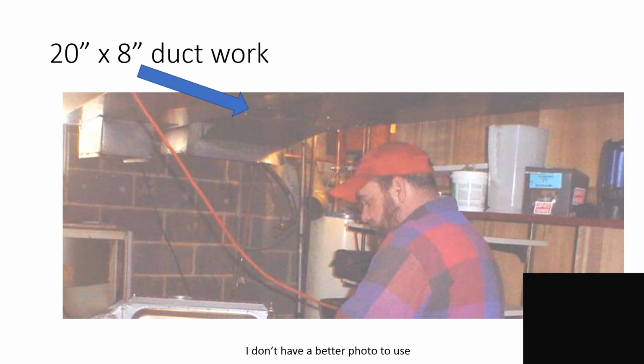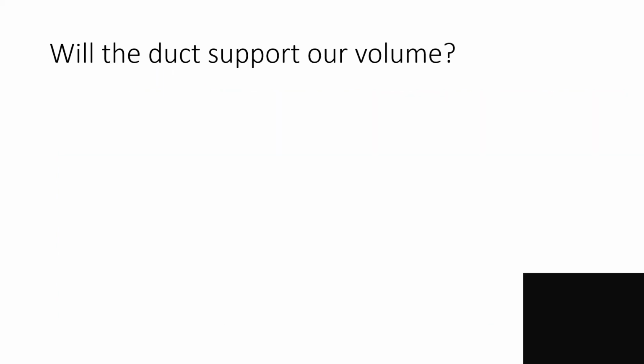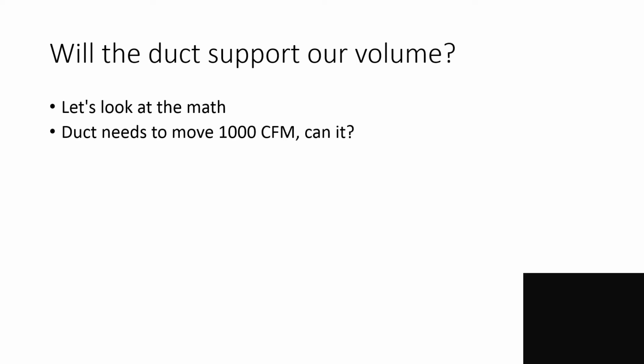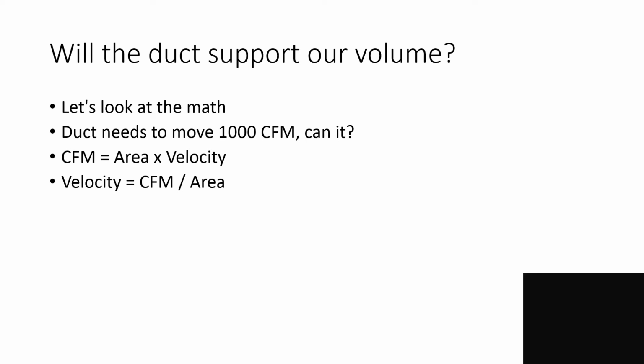We got 20x8 ductwork on an existing system and we're replacing it. So let's determine if that 20x8 ductwork is large enough to move that 1,000 CFM that we just calculated. So will it? Well, let's look at some math, right? The duct needs to move 1,000 CFM. Can it? Well, CFM is equal to area times velocity. That's a fact, right? That's not going to change. We can manipulate that formula into velocity being equal to our CFM divided by our area.